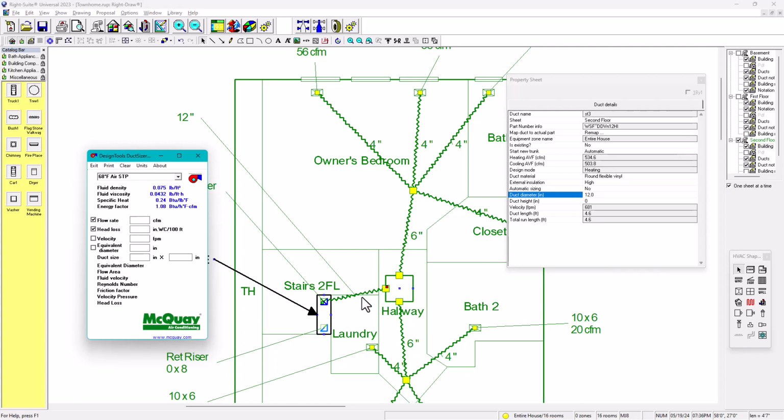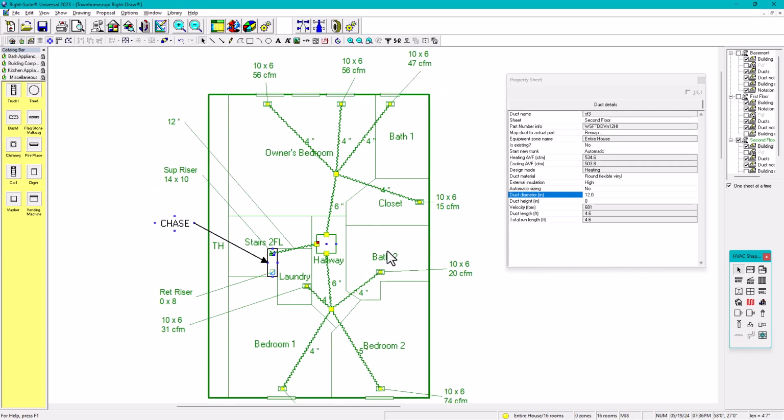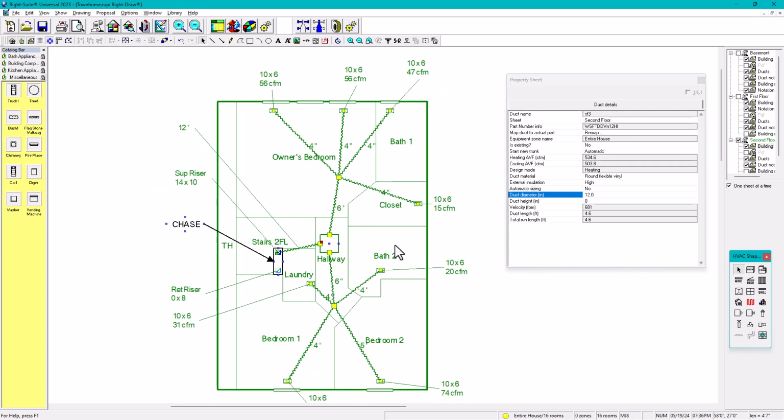So in here, what's the CFM? That is the tricky part, because if you want to size with a duct calculator or this online ductulator, you need to know the CFM. What is the CFM that you're going to have in here? The issue in Wrightsoft is that this is not simultaneous heating and cooling. This is black or white, either heating or cooling. It's a heat pump, heating only, cooling only, not mixed, right? Not both.